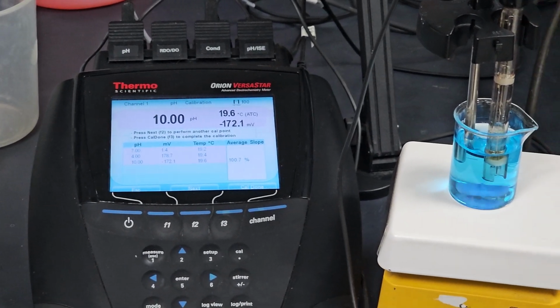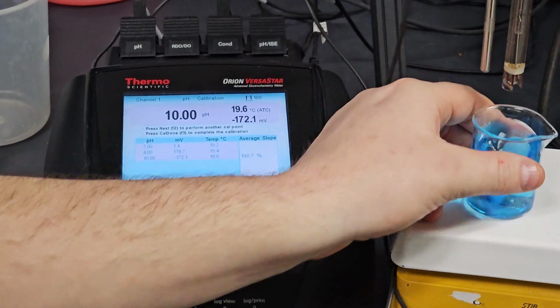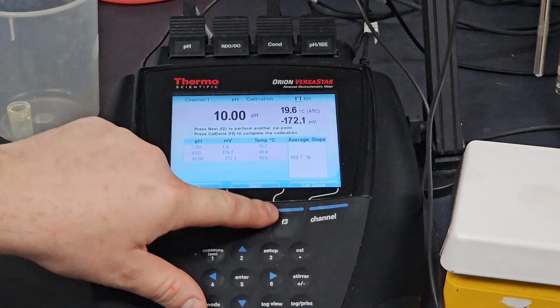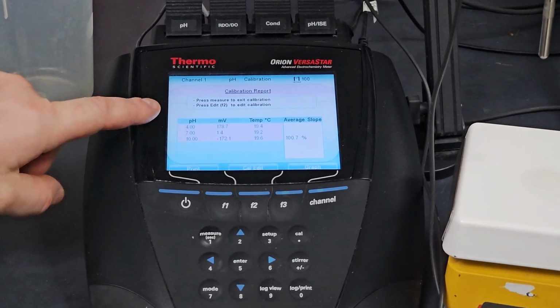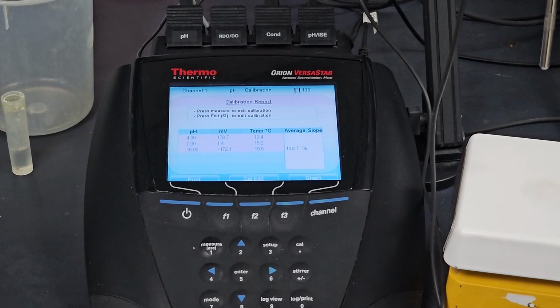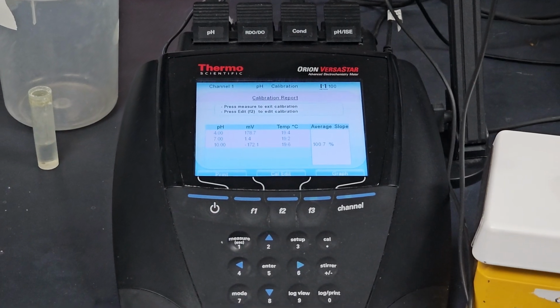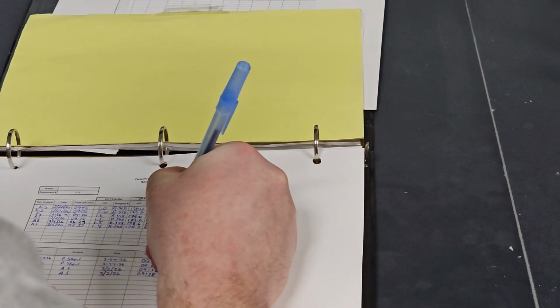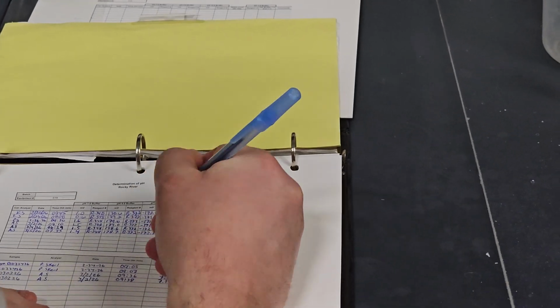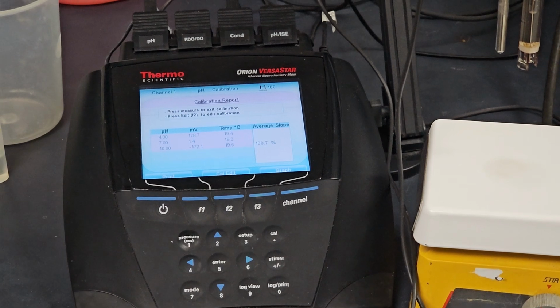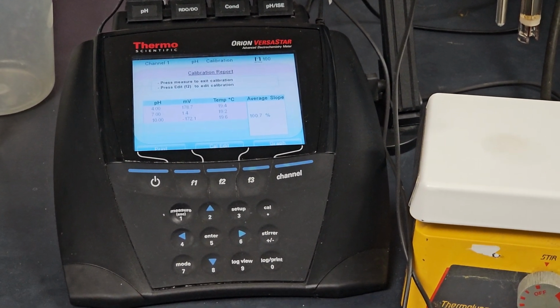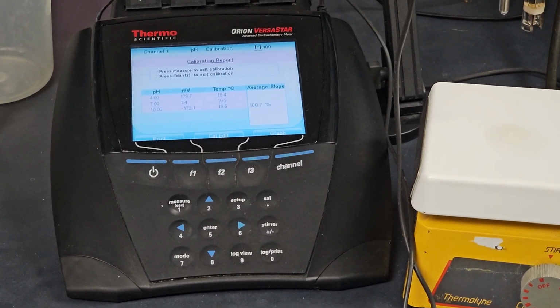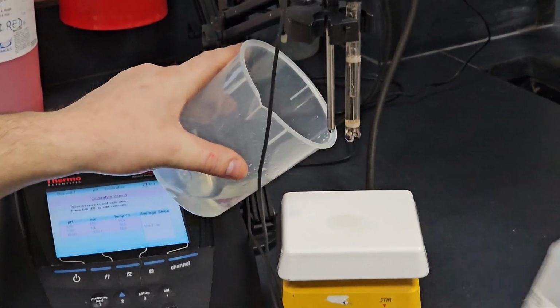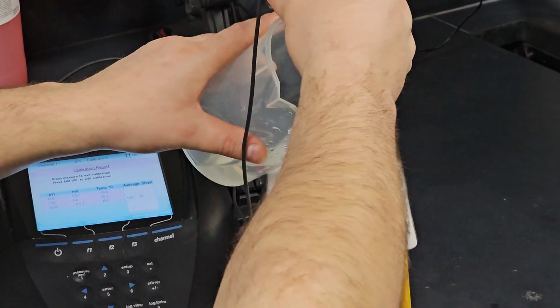Now that is all of our buffers, so we can remove the probe from the buffer, and we will hit Cal Done. At the end of the Cal Done, you'll see you have achieved a slope. You want to record your millivolts for the 10 buffer, which was -172. This will most likely always be a negative number. And our average slope, which was 100.7. We will rinse the 10 buffer off of the probe. Gently shake the excess.